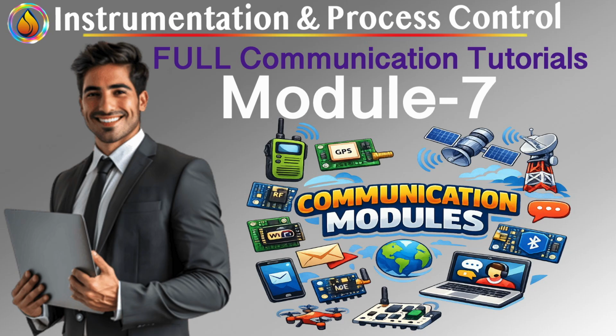Publisher-subscriber, not request-response. Notice how different this is from polling. In Foundation Fieldbus, a device publishes data, and multiple devices can subscribe to it. Data is identified by content, not destination. The tutorial explains this clearly. Scheduled data transfer allows one device's data to be used by multiple subscriber devices. This is incredibly efficient. One transmitter's output can feed control loops, displays, diagnostics, and logs all at once.